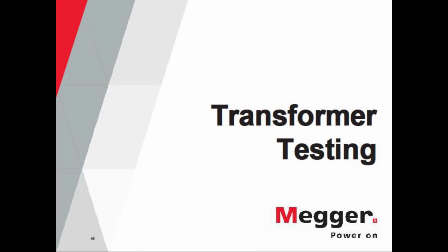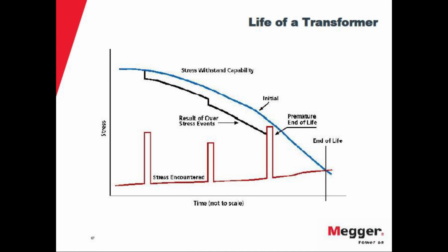So for transformer testing, power transformer testing, well, the idea is that this is the curve of the life of a transformer with no operation. Basically, if you leave the transformer sitting, at a certain point it will have an end of life. But a transformer in operation has a different curve. So every time there's a stress or an event in the system, that will affect the life of the transformer. And at a certain point, there will be an event that is very stressing, and that will end the life of the transformer. So you want to perform periodic testing so that you can do something and improve the characteristics of the transformer, so it can have an extended life.